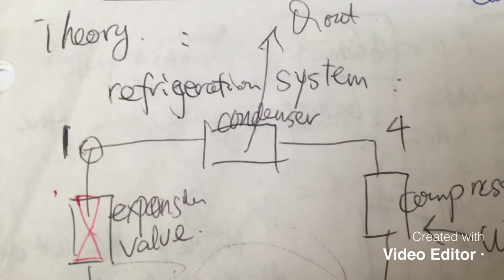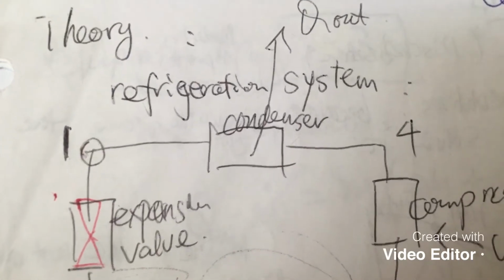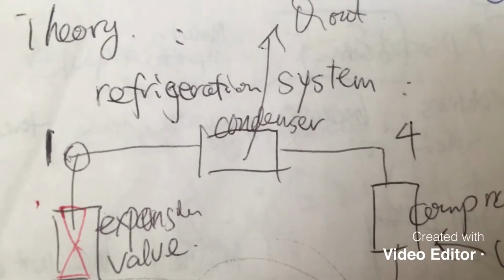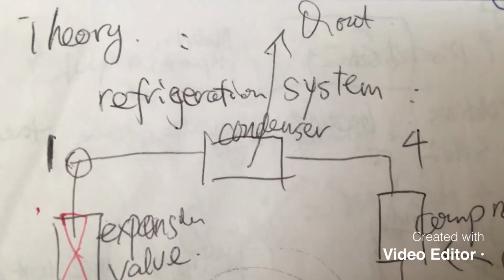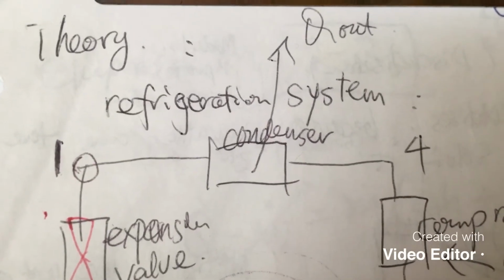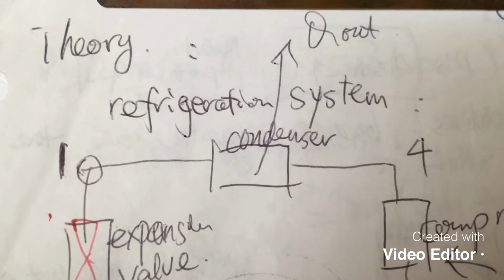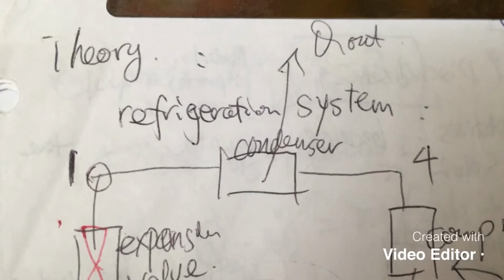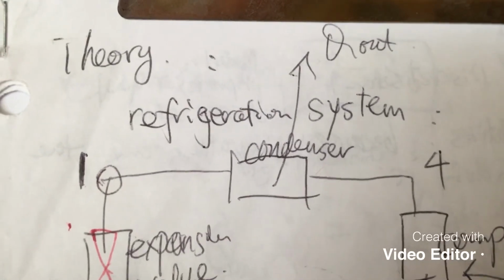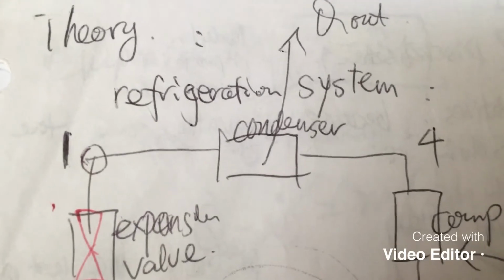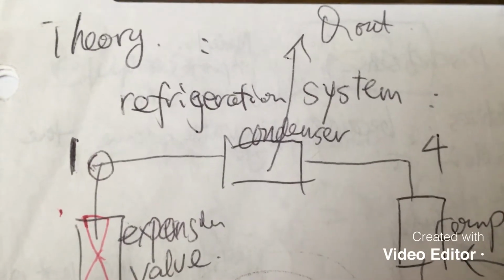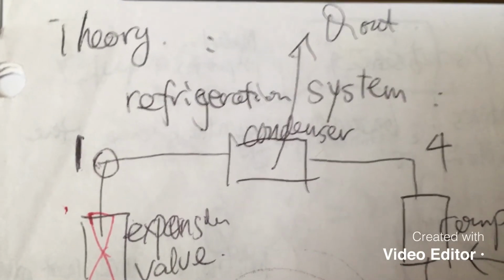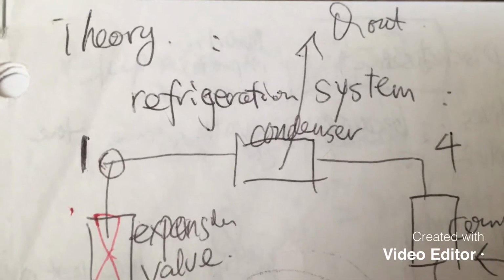M dot is the mass flow rate of the water. So mass flow rate of the water is displayed on the unit, so you will see that value. Delta T is what you need to measure. The water is just room temperature water entering the condenser, so it's room temperature, about 75 degrees. Then the water leaves the condenser hotter, right? So you will need to measure that water temperature. So you have the delta T, you can find it. And the mass flow rate of water is shown, okay? So the total heat gain in the water side can be calculated.